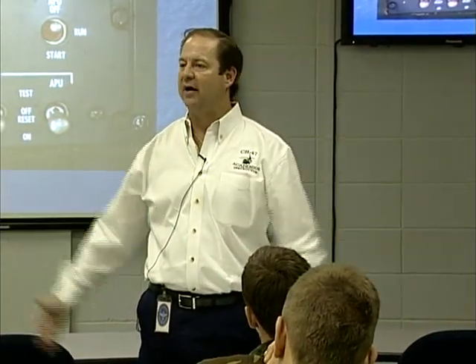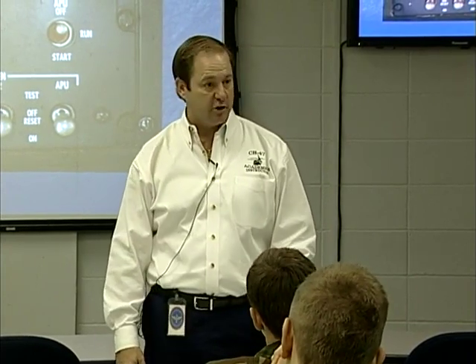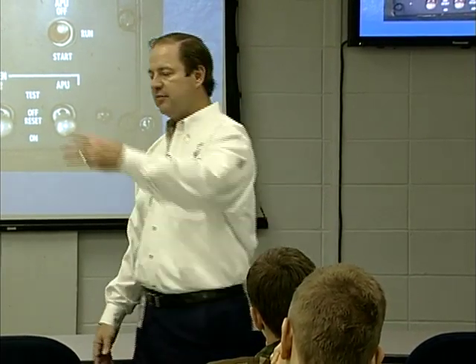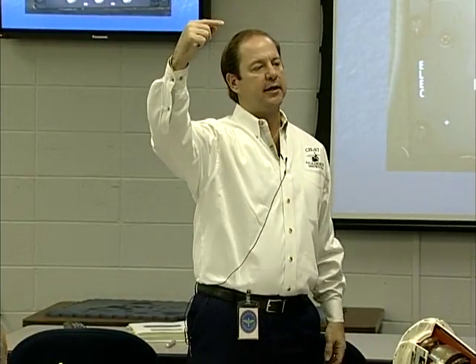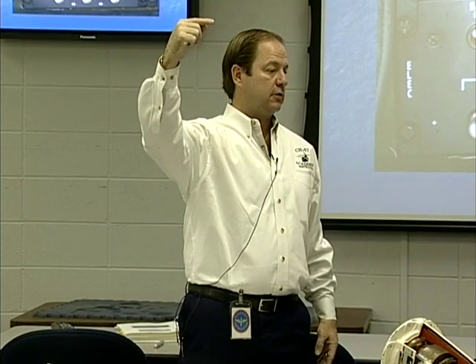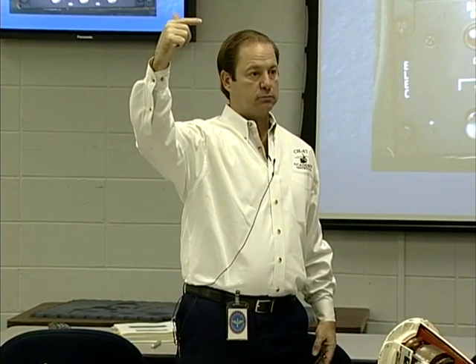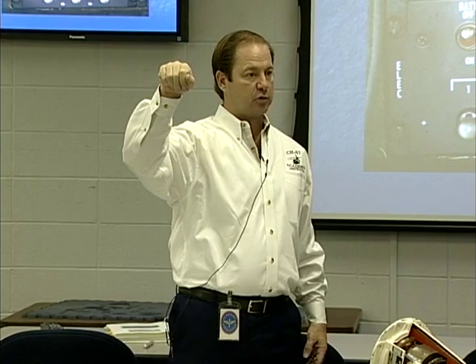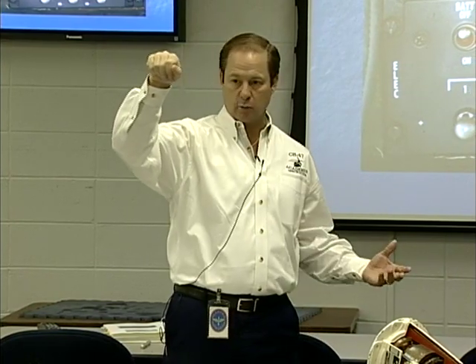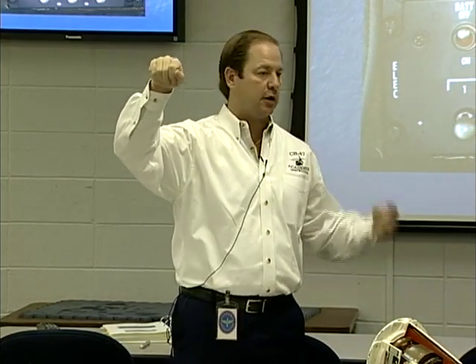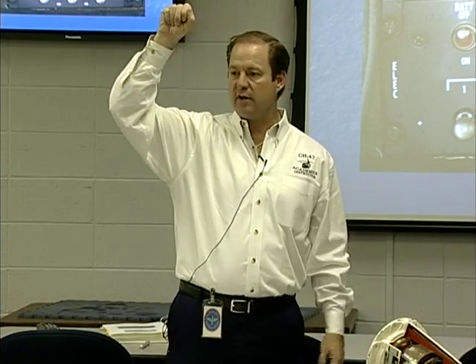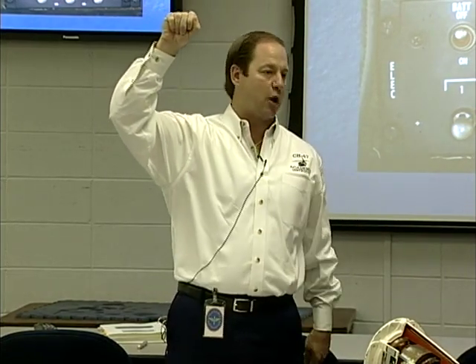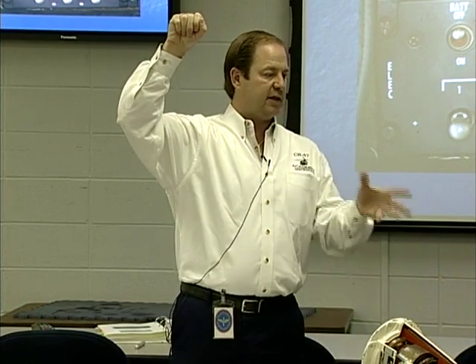What's the only thing you have? The generator off caution capsule. So if it doesn't sense any of those problems, that light is now going to come back or go back out. The generator off caution capsule came on because the generator was off. I went through the off reset, it turned it off. Go to the test position, that light's going to go back out. If it doesn't sense an over voltage, under frequency, or feeder fault, it's going to turn the light back out.